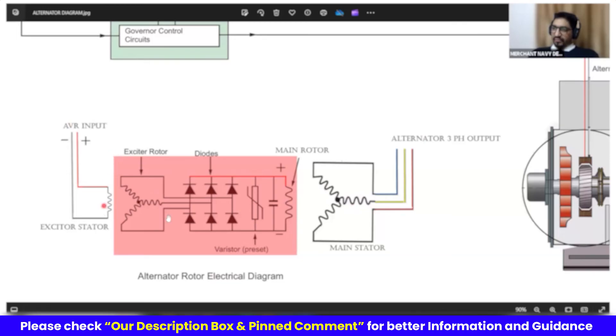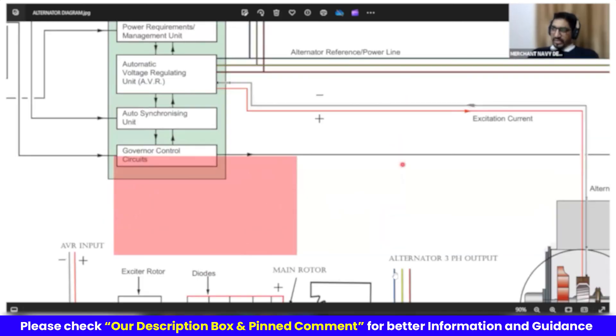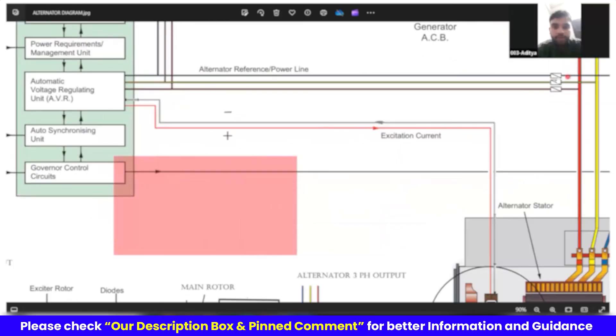Point here is AVR gives DC to here. It produces AC here. This AC comes back as a DC here. And this DC is used to produce AC here. And this is what we use. Your question is, who gives DC to the exciter? AVR gives it. Where does AVR get this one from? From output only.